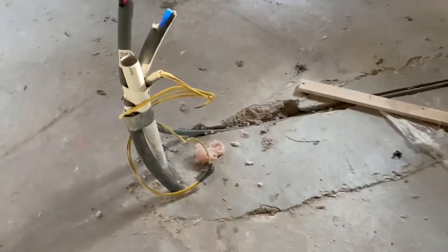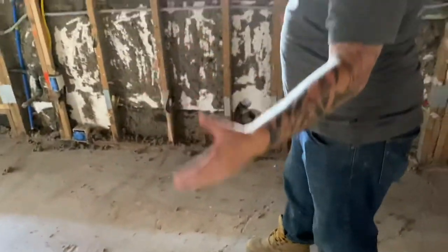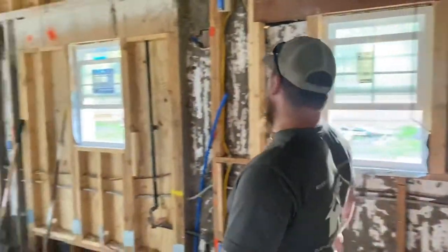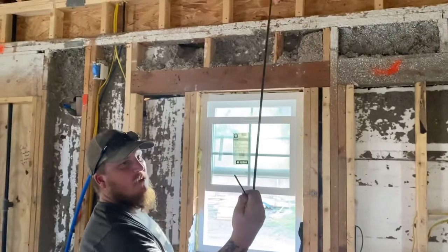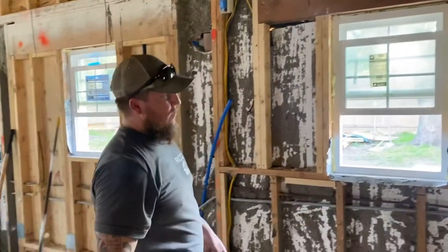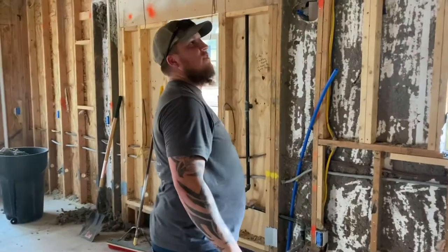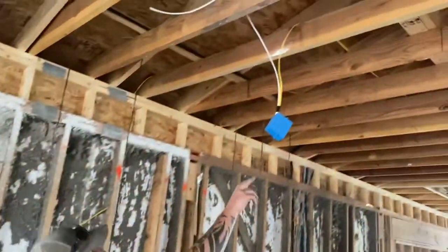You've got what appears to be conduit up above grade — that's going to be really fun to floor over. We now have to break this concrete back up and put new conduit under the ground. They used speaker wire for lighting systems, which creates a huge fire risk. You should always use 10-2, 12-2, 12-3, whatever the code is for the area. They had hidden J-boxes, electrical, sitting up in the attic.